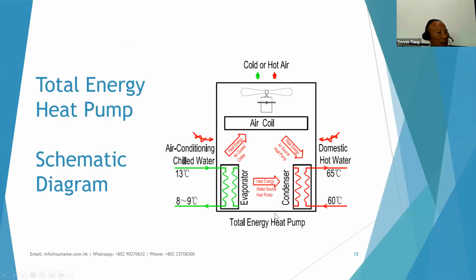So this is the schematic diagram of a total energy heat pump. There will be more heat transfer units inside. There will be an evaporator, a condenser, and an air coil. So this is the combination of an air-to-water heat pump and a water-to-water heat pump.